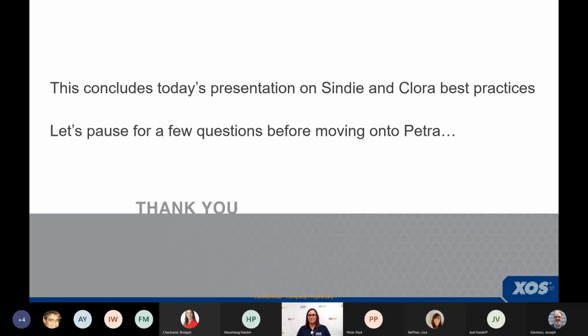Would you recommend cleaning the pins for puncturing holes in sample cups between running different samples? Absolutely, I would recommend that, especially if you're switching between high concentration and low concentration samples. That's actually one of the reasons that we recommend when you're calibrating that you start with the low concentration sample first, because it's then less likely to contaminate the other samples. So if you forget to clean that push pin, the other thing is some people will just use a new push pin for each sample. Up to you, but yes, that's a very good idea to clean the push pin.